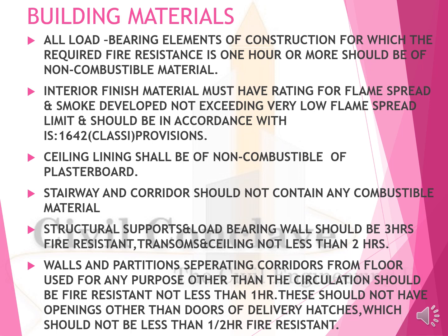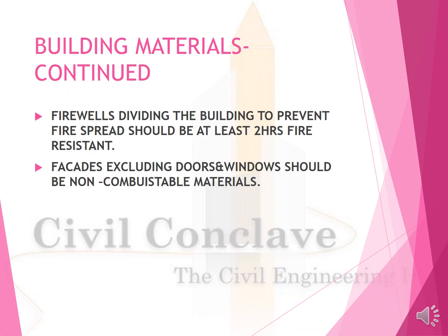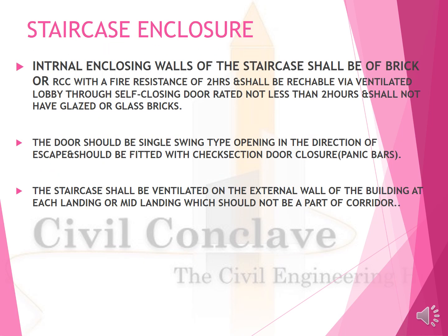Walls and partitions separating the corridors from the floor should have a fire resistance of not less than 1 hour. These should not have any openings other than the doors or delivery hatches, which should have not less than half an hour fire resistance. Fire walls dividing the building to prevent the fire spread should have at least 2 hours fire resistance. Facades, excluding doors and windows, should be a non-combustible material.